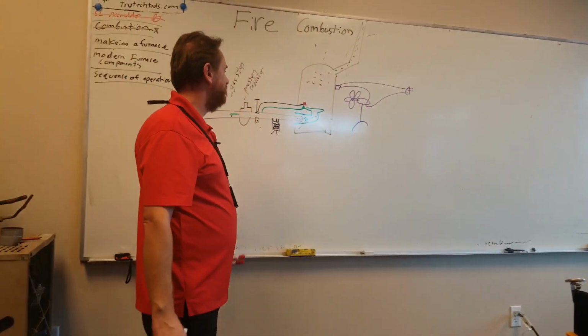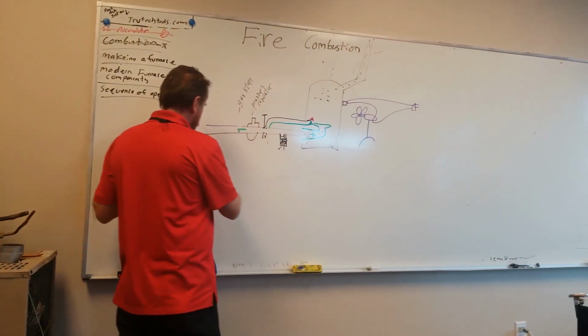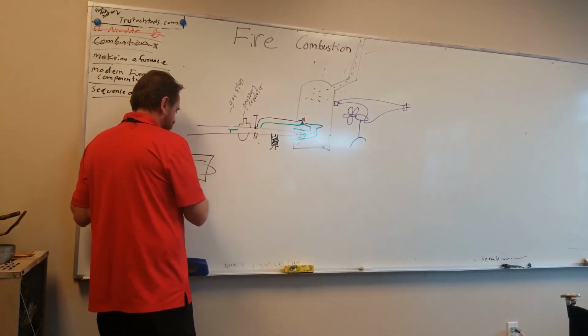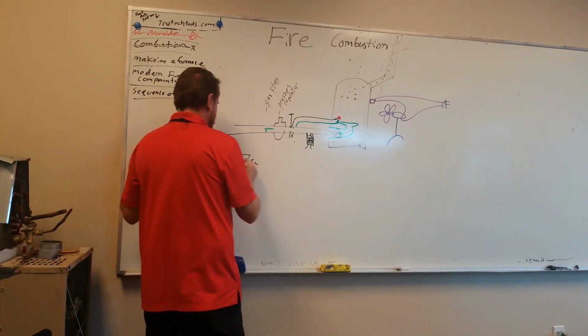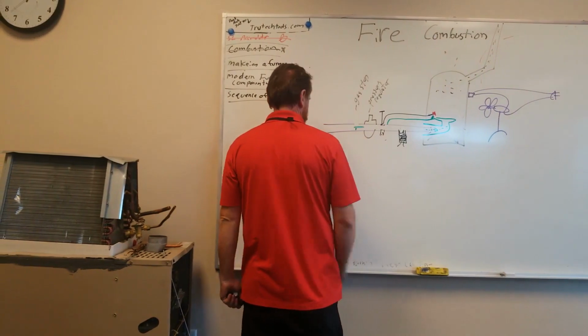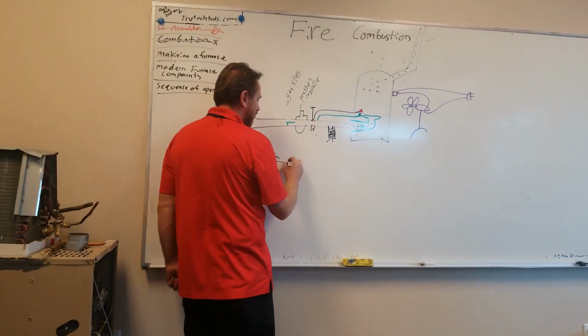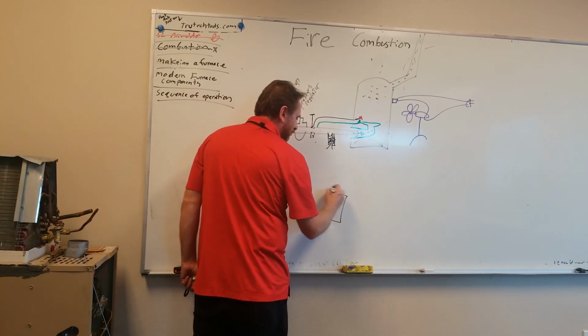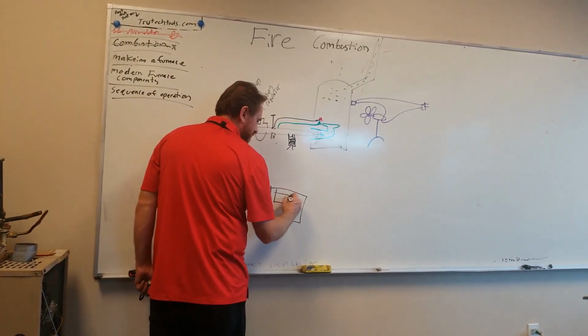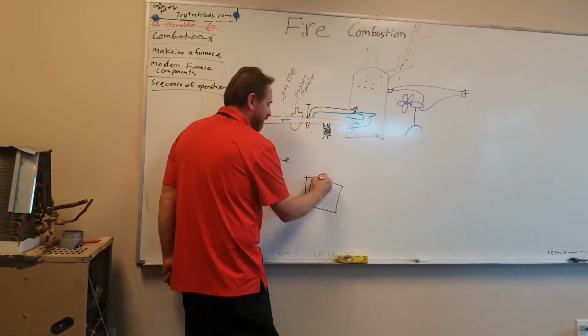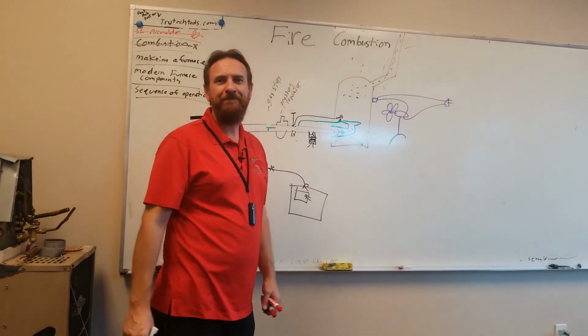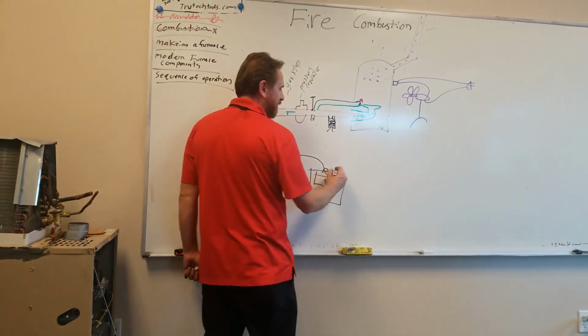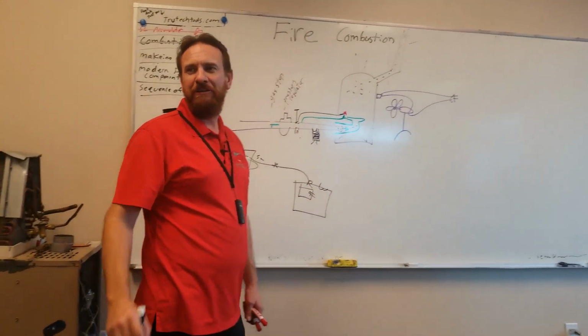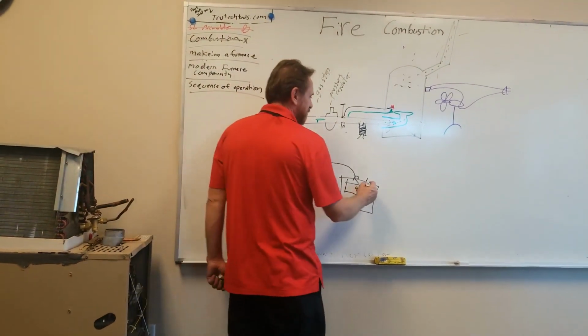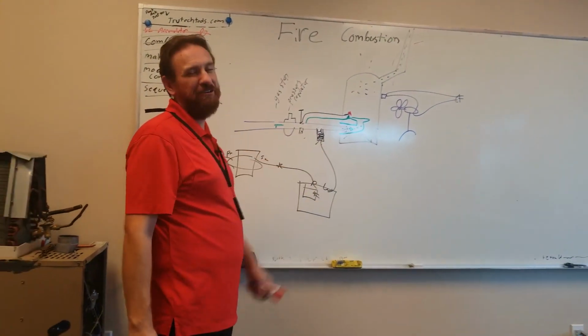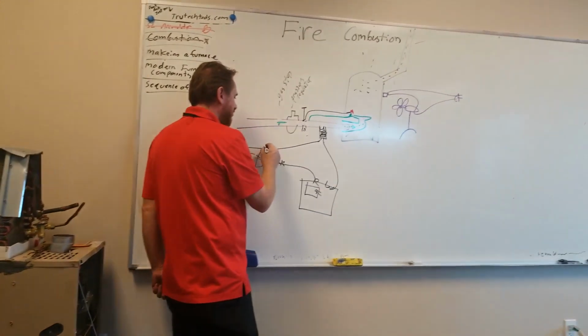Then, I need something to control it. So let's put a transformer over here. So over here we're going to have primary and secondary. Primary plugs into the wall outlet. Secondary, we're going to have the letter R coming out of it. What if we hook that R wire to our thermostat? So we have the R wire from the transformer to the thermostat, so that when the thermostat had a call for heat, it would connect it to the W wire. Where do you think we'd run that W wire? To the solenoid valve. And after we do work in the solenoid valve, where should we go? Home, 24 volt coming to the transformer.